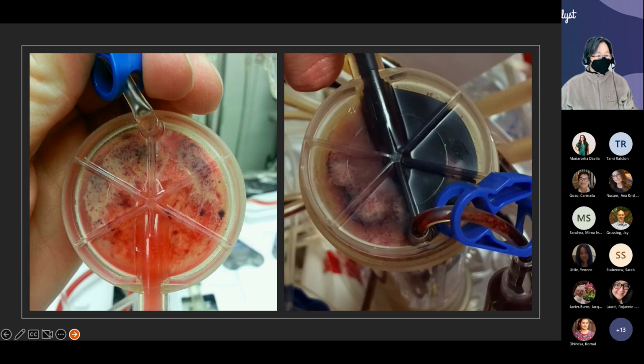You can see there's some white precipitate at the top, which is fibrin deposition in the header, likely due to some turbulence. You'll see that start to occur, and if you let it go on and on, in the next window over you'll see clotting of the dialyzer. In general, you will occasionally see this in a dialyzer.